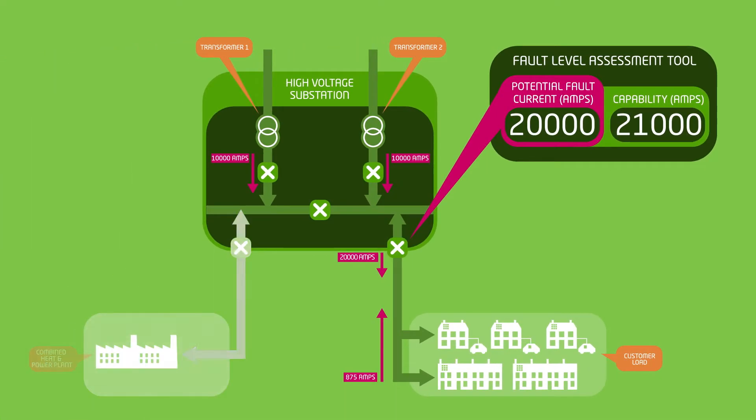But what if we need to connect additional demand or generation to the network? This will increase the total potential fault current to above the capability of the high voltage circuit breaker, leaving the substation vulnerable to damage if there's a fault.